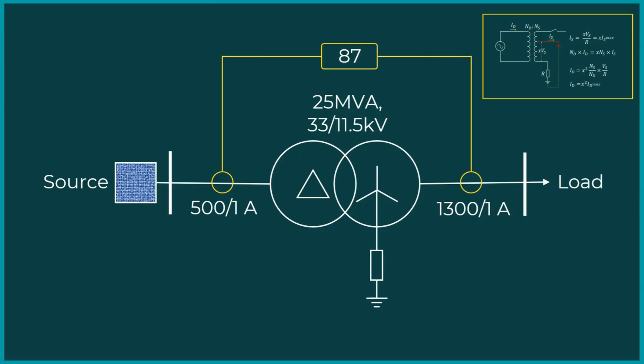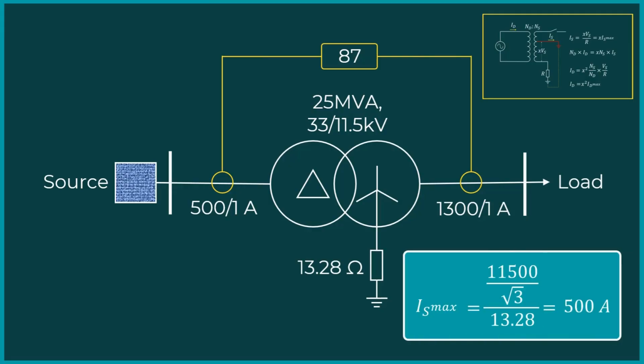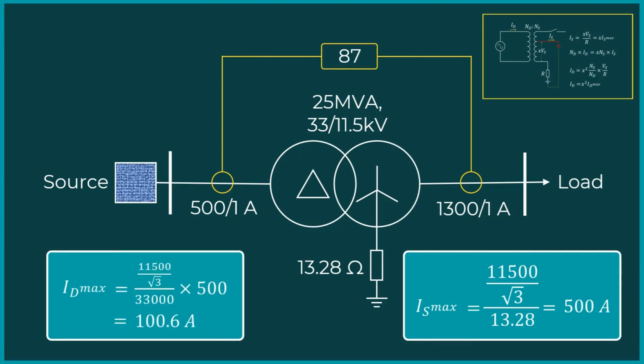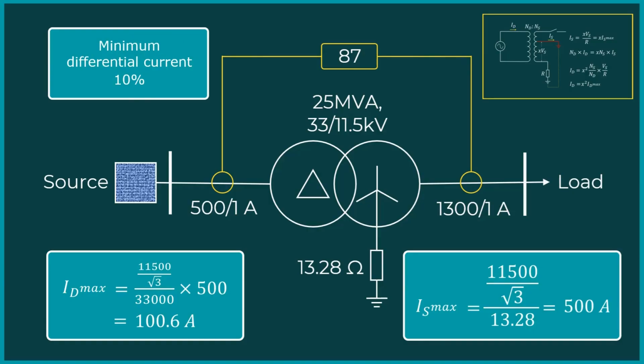Transformer star winding neutral is grounded through a low resistance value of 13.28 ohm so that the star side earth fault current is limited to 500 ampere, and hence the corresponding delta side current will be 100.6 ampere. The minimum differential current pickup setting is set at 10%, and hence at least 50 ampere of current on the delta side is required for the 87 element to operate.